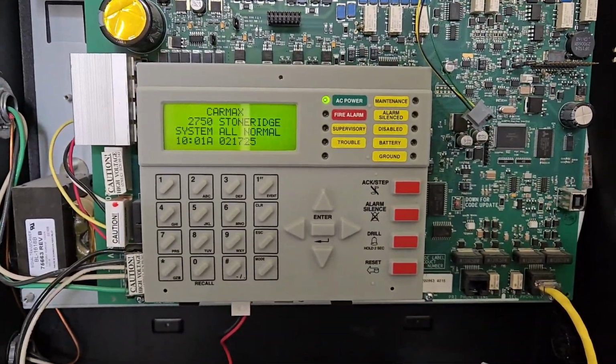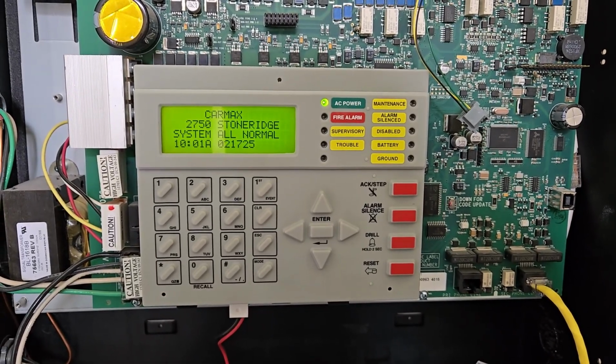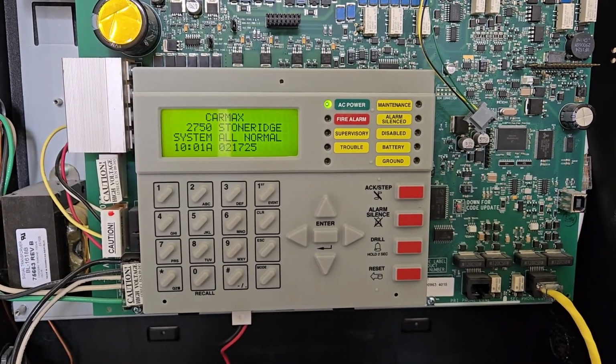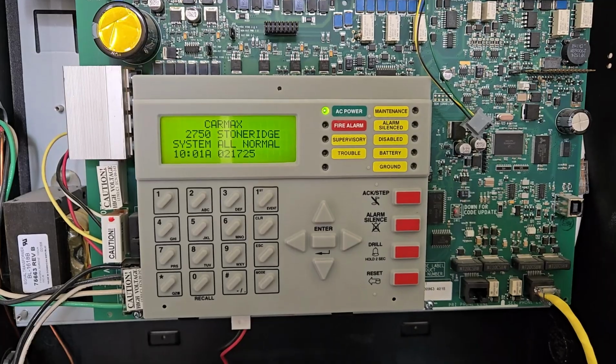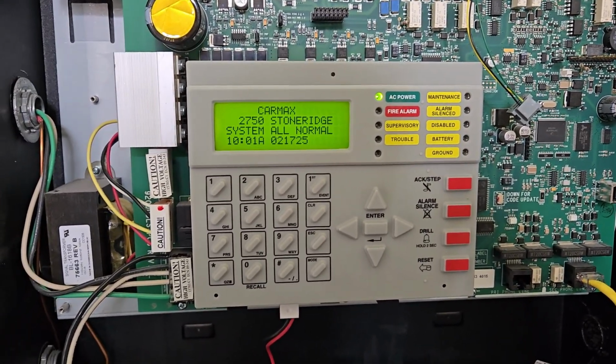So if your fire panel does not receive a phone line signal within 4 minutes, it's technically a fail, but you could always retest to see if it is a timer issue or it was just a one-off or it didn't come in right away the first time. But within 4 minutes is the goal or the code.